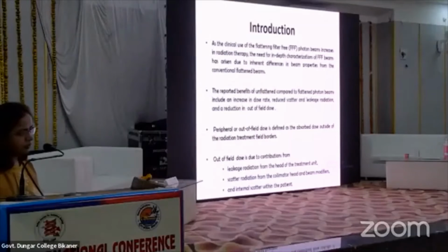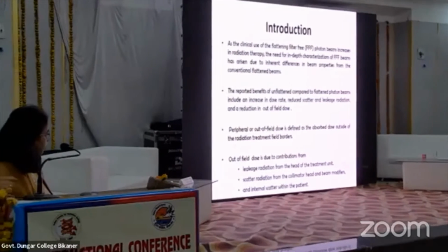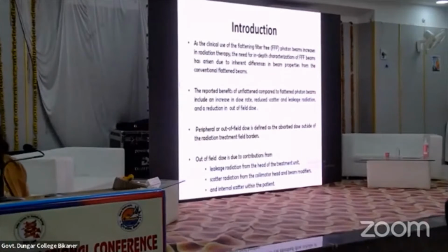Introduction. As the clinical use of flattening filter-free photon beams increases in radiotherapy, the need for in-depth characterization of FFF beams has arisen due to the inherent differences in beam properties from the conventional flattened beams. FFF is one of the advanced treatment modalities available in linear accelerator machines. The reported benefits of unflattened beams compared to the flattened photon beam are increased dose rate, reduced scatter and leakage radiation, and a reduction in the out-of-field dose.